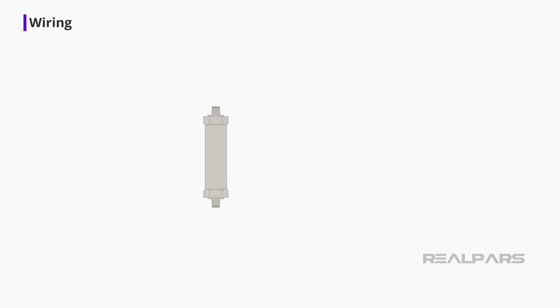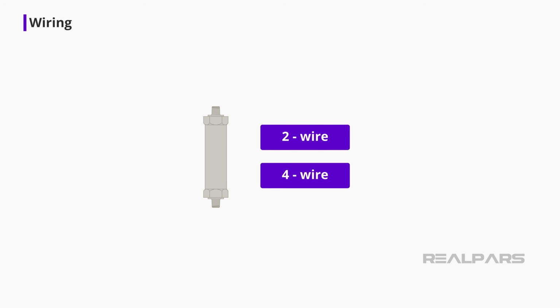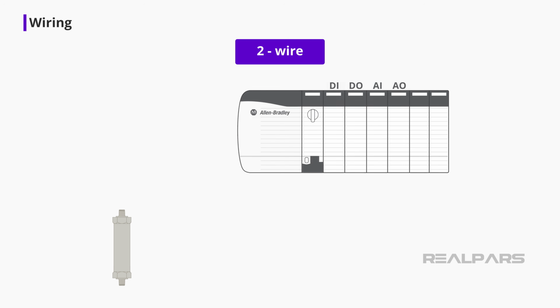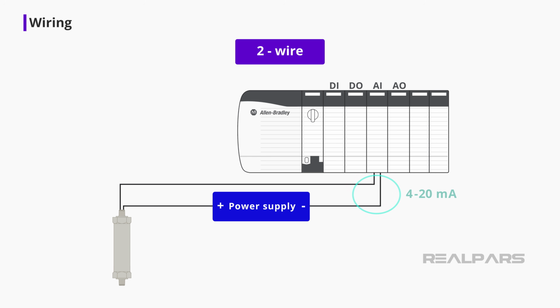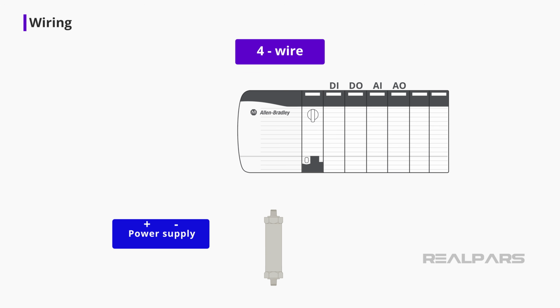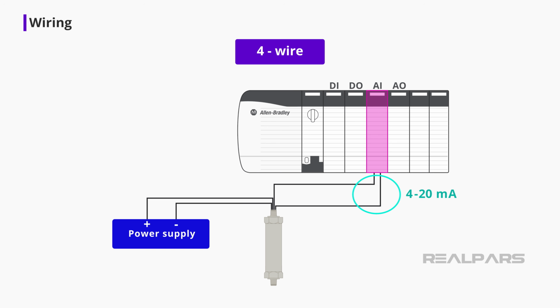A pressure transmitter requires a power supply to operate. Most pressure transmitters are two-wire types. Transmitters are also available as four-wire types. As the name suggests, a two-wire pressure transmitter has only two wires. These two wires provide power for the transmitter and are also the signal lines. A four-wire transmitter has two wires connected to a power supply and two signal wires connected to the PLC. The power supply can be AC or DC depending on the vendor and model.